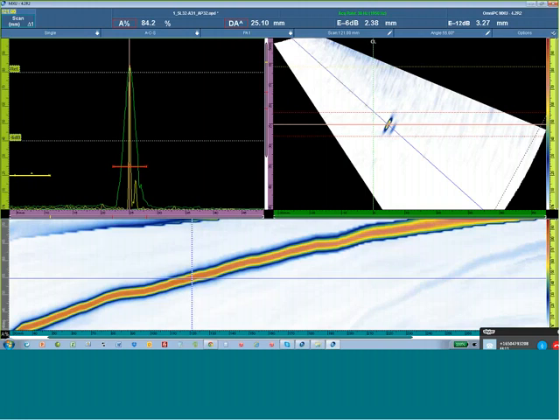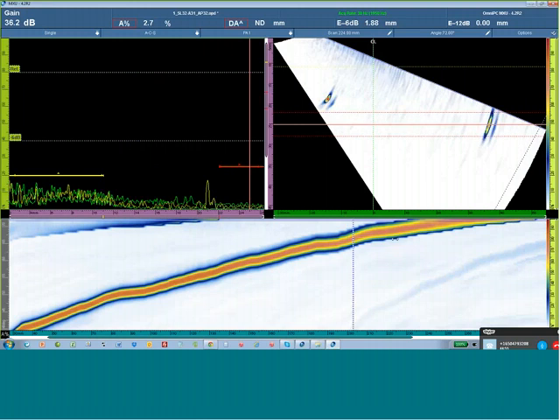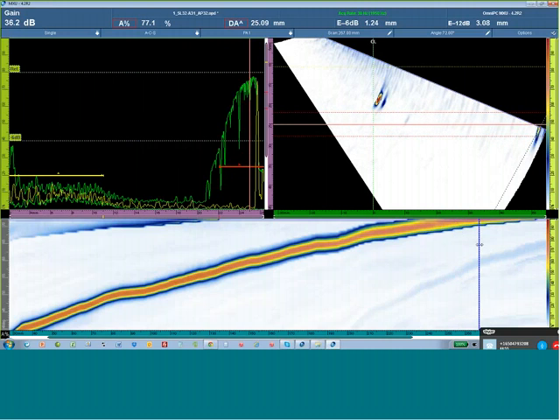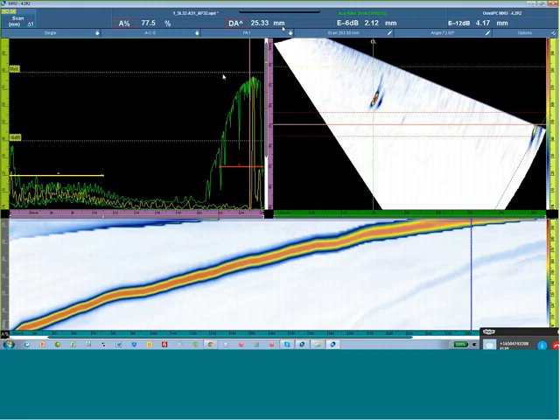When I take the data cursor or do it live on the block, the first thing I'm going to look for is my ability to maintain the correct depth at focal law 1, which is the 40 degree here, all the way through to the nominal wedge angle. We're looking for the center of the energy directly in the middle of the target at the correct depth calculated by the trigonometry for the amplitude signal in gate A. And then we're also going to take this all the way over to the last focal law, in this case, 72 degrees. The envelope signal allows us to see the peak data and peak up the signal. So in this case, the trigonometry is correct because the angle is correct. And we can do that for all of the A-scans throughout the S-scan.